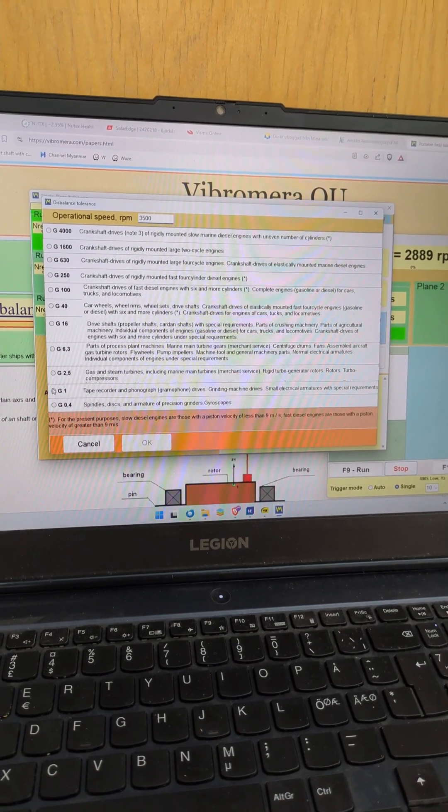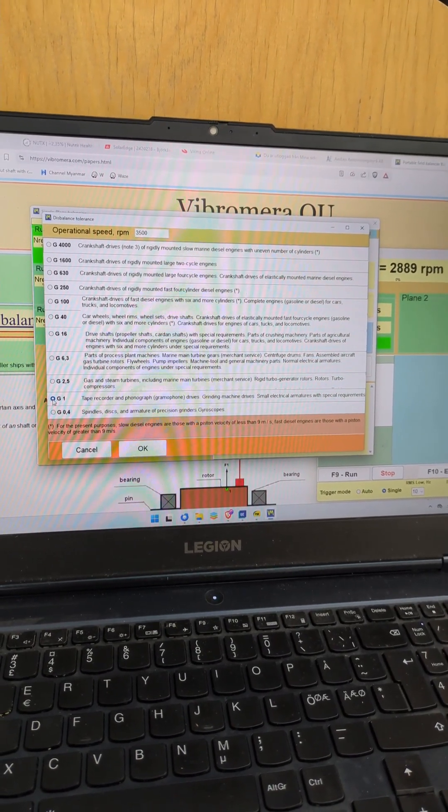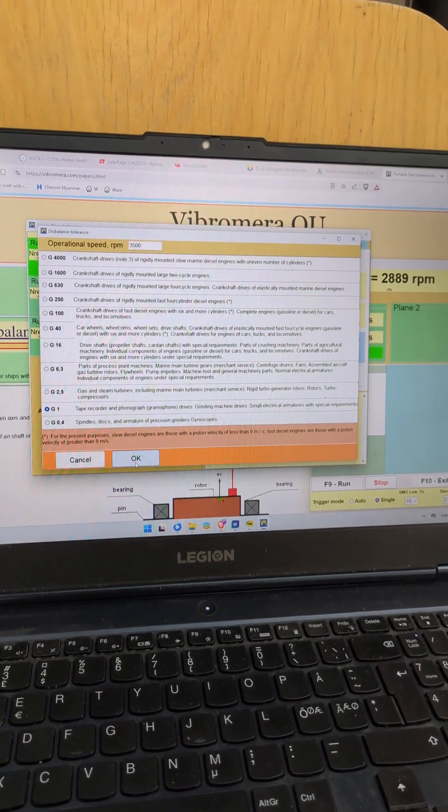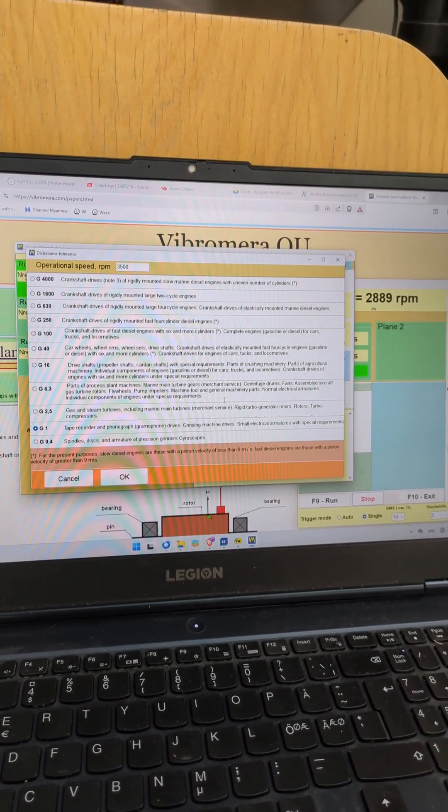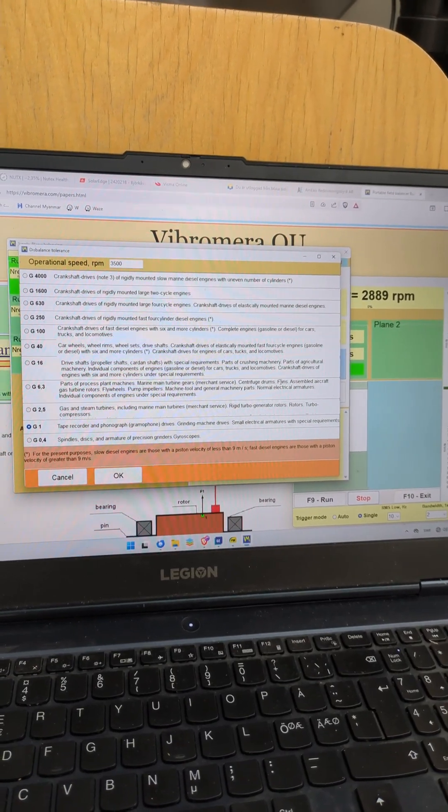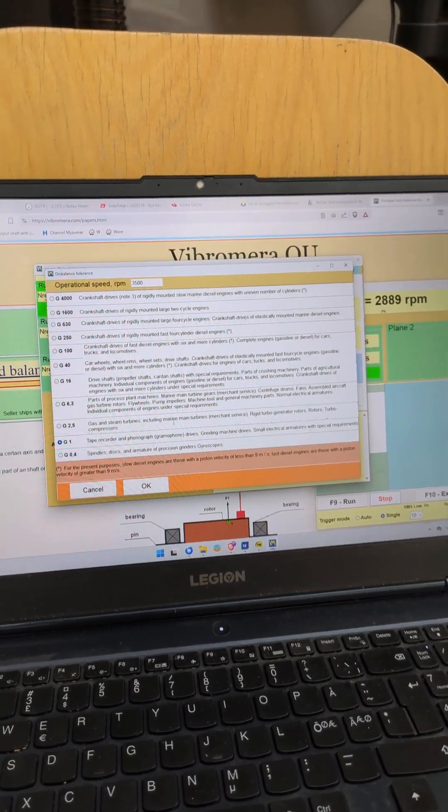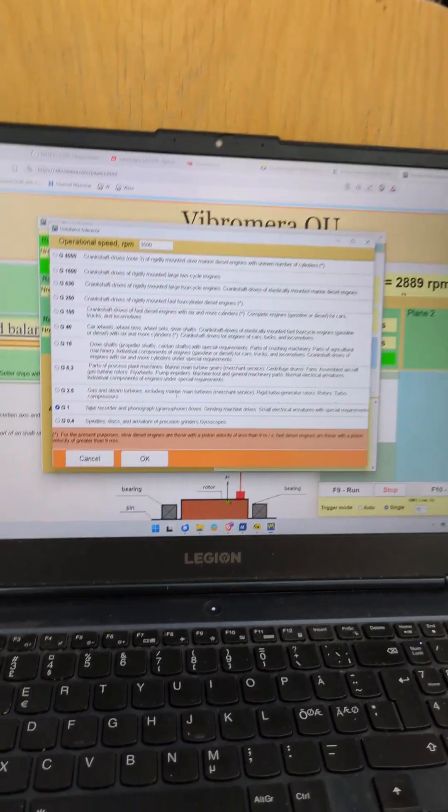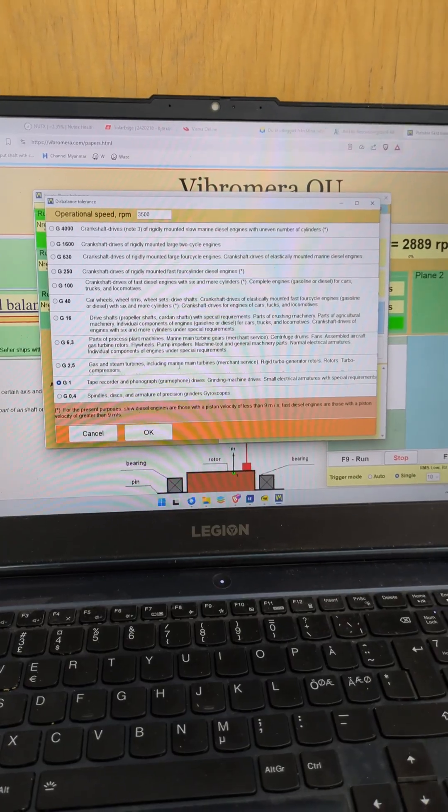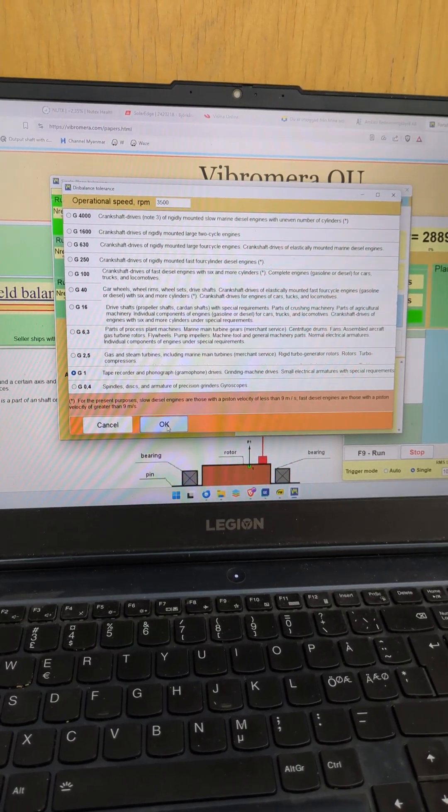And it's going to run on 3500 rpm. And we'll aim high. We aim at the G1. Typically a fan is on G6.3 and 2.5 would be fantastic but just to see that is possible. We aim for G1.